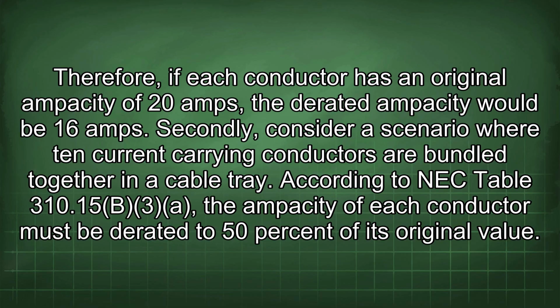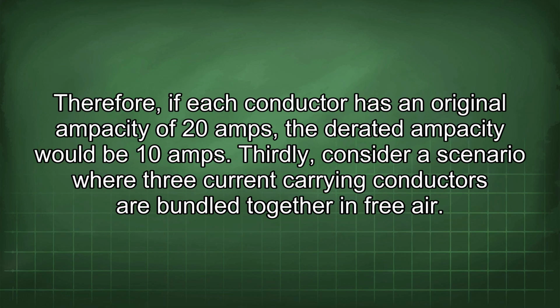Secondly, consider a scenario where 10 current-carrying conductors are bundled together in a cable tray. According to NEC Table 310.15(B)(3), the ampacity of each conductor must be derated to 50% of its original value. Therefore, if each conductor has an original ampacity of 20 amps, the derated ampacity would be 10 amps.